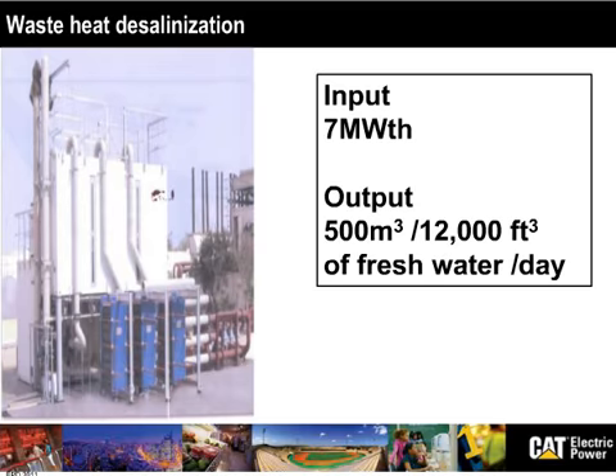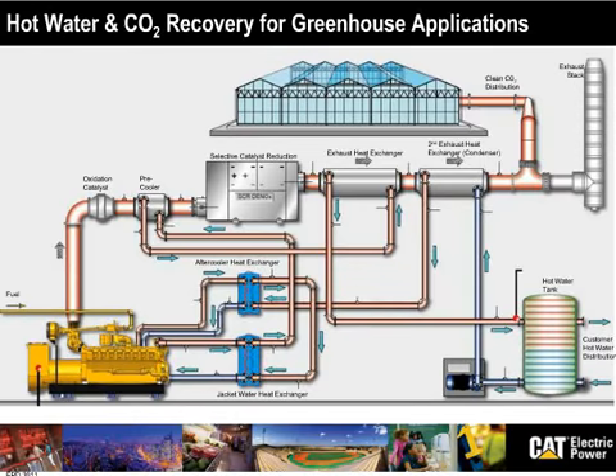More heat again, and we've used the heat from the genset to produce hot water. We used the heat from the genset to produce steam, fresh water. What else can we take from the genset? And here we go. What else is CO2? CO2 and heat recovery is very popular in greenhouses, and you see the complex heat recovery system to take all the kilowatts of heat from every circuit in the genset for the greenhouse. But in the middle of the chart here, you see a selective catalytic reductor, and this will actually clean the exhaust gas of the genset to a point that you can actually insert these gases when they're cooled directly in the greenhouse. They're virtually pure CO2.